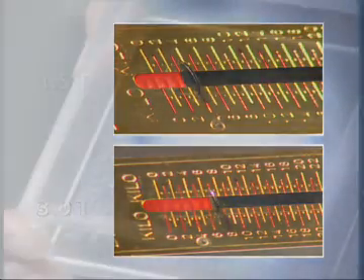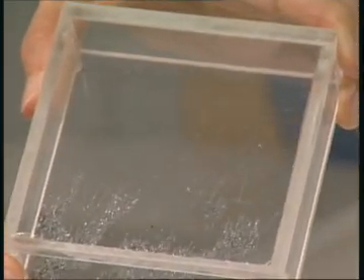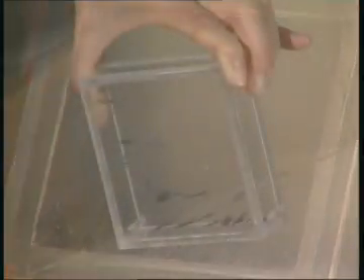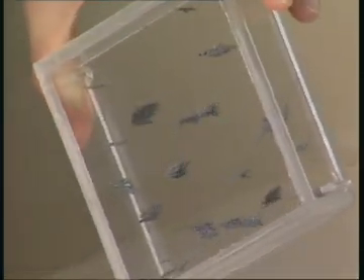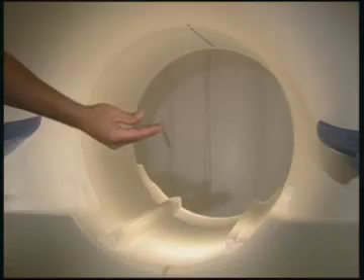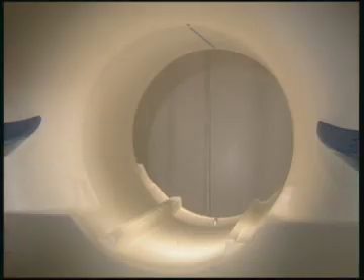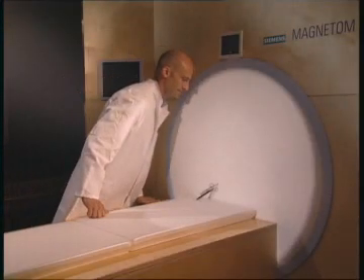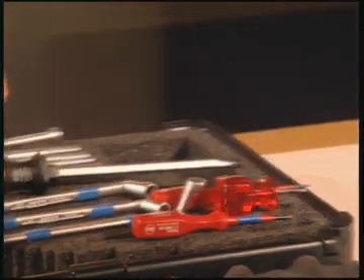Magnetic fields from magnetic resonance imaging systems are not directly perceptible, and their dangers are often underestimated. They exert an enormous attractive force on magnetic objects and objects containing magnetizable material. Can you imagine approaching the magnet with a set of keys in your pocket? Or forgetting to remove change, your lighter, or your pocket knife? And what about the dressing scissors? Ferromagnetic objects are attracted by the magnet and often cannot be held back. See for yourself.